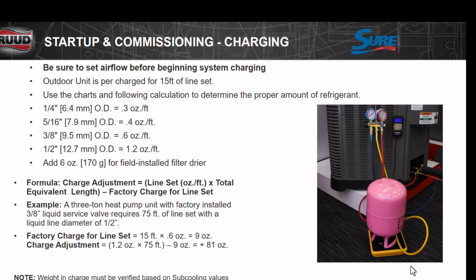Now, the other thing is, we always talked about the best way to charge a system is to charge it per manufacturer specs, right? But in doing that, we want to be sure that we're not flooding our unit back with liquid, okay? Because if we fill it up with liquid and crank it up, it could be a goner. So we want to let it sit down and rest a little bit. All the refrigerant finds its way.